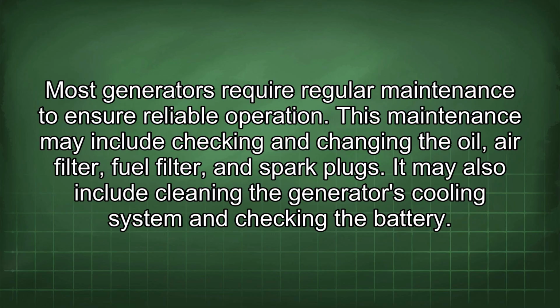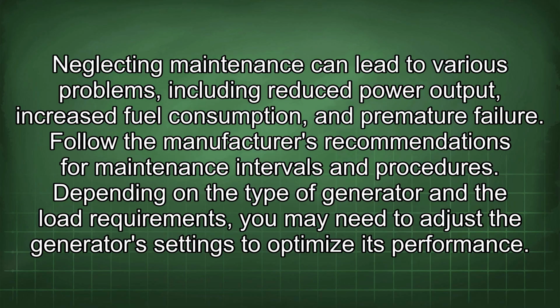Most generators require regular maintenance to ensure reliable operation. This maintenance may include checking and changing the oil, air filter, fuel filter, and spark plugs. It may also include cleaning the generator's cooling system and checking the battery. Neglecting maintenance can lead to various problems, including reduced power output, increased fuel consumption, and premature failure. Follow the manufacturer's recommendations for maintenance intervals and procedures.